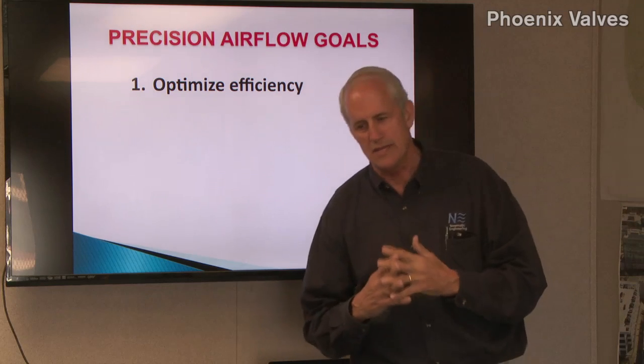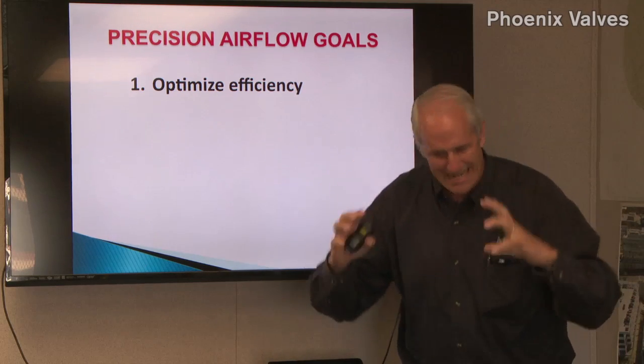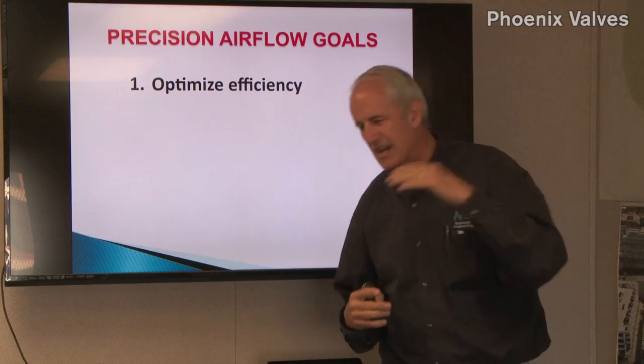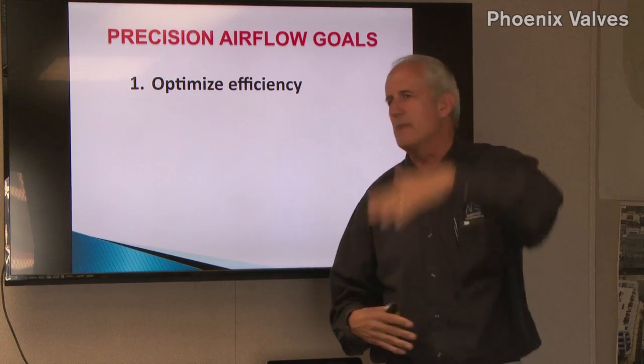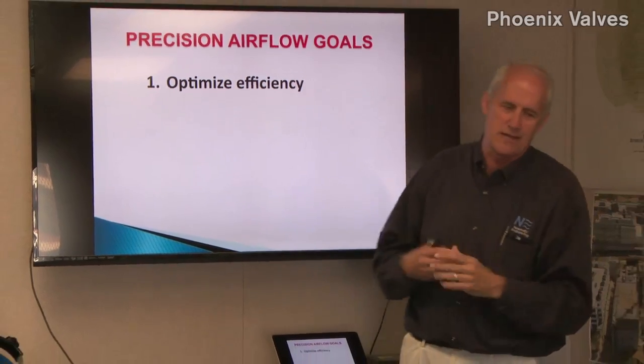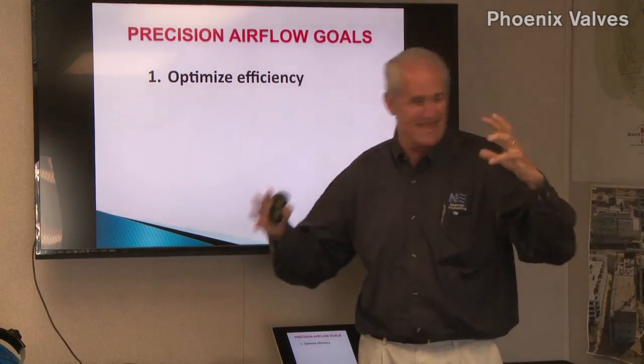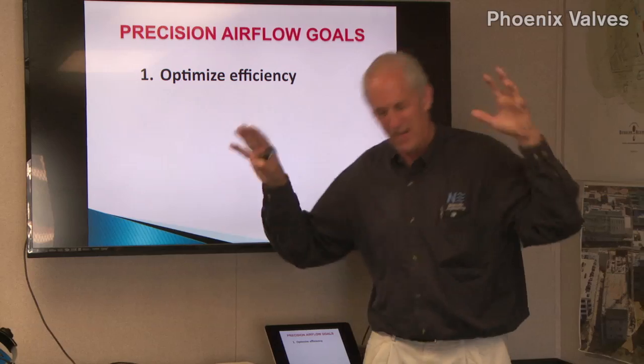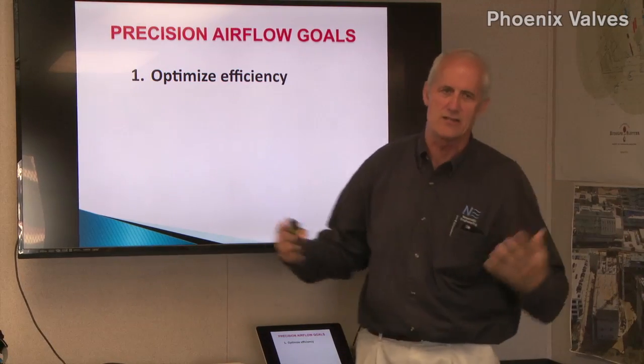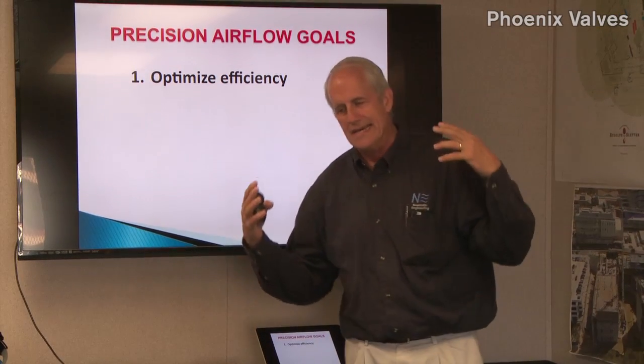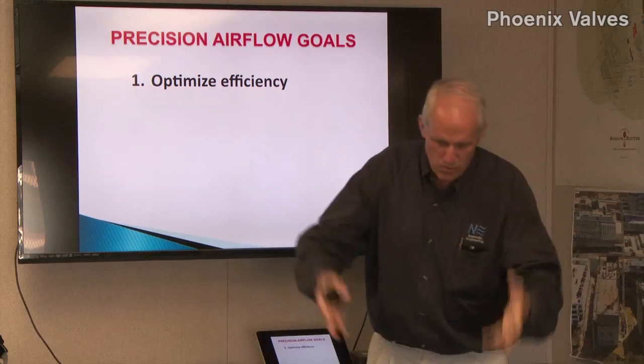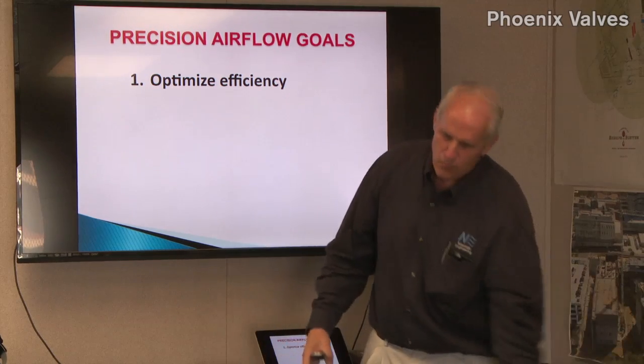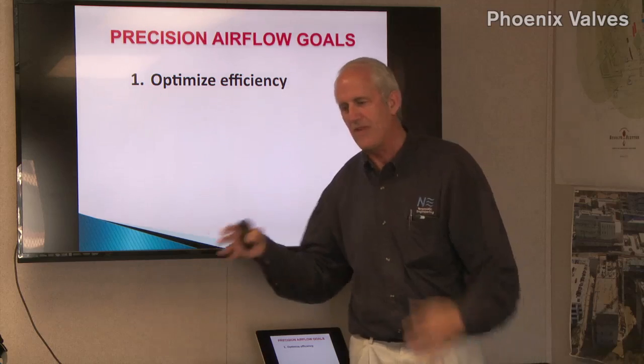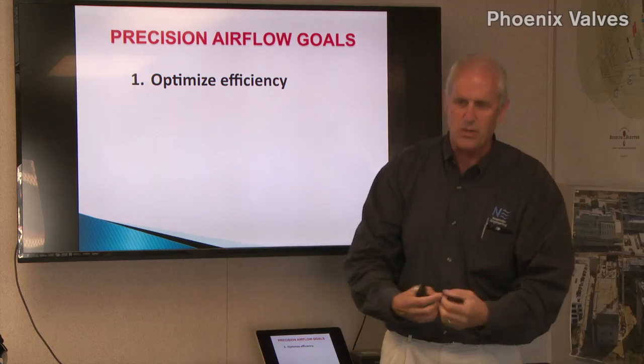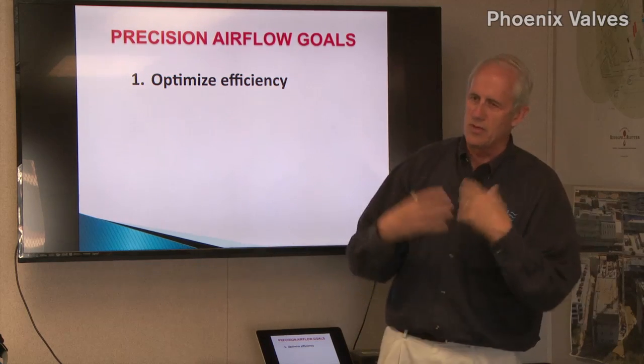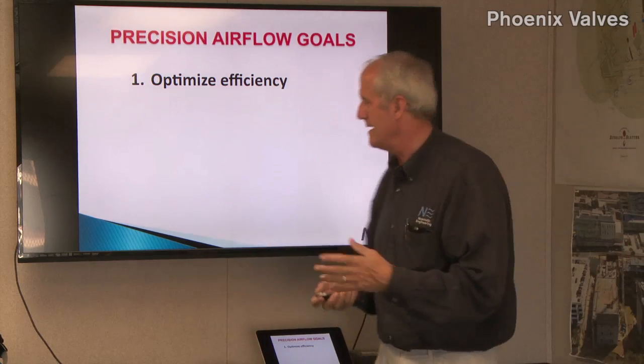The reason you do that is because you need really good temperature control. If you say, oh, I'll take my discharge air, I'll bring it up to 65, supply air temperature reset, you can do that, but then you've got a couple of zones that need every drop of that 55-degree air, and now you start losing control of your zones. So you design with a lot of cold air, most of which is reheated. By putting in Phoenix, you can vary the volume. You can reduce the volume of air. Now you're reducing both the cooling and the heating and the fan power, and everybody wins.